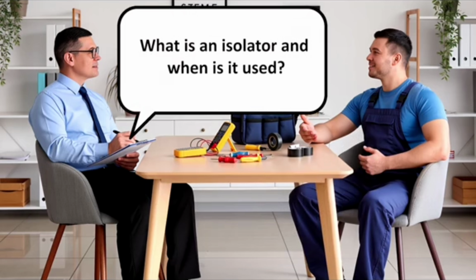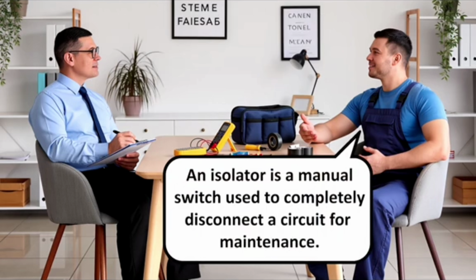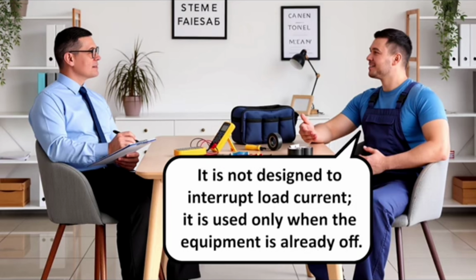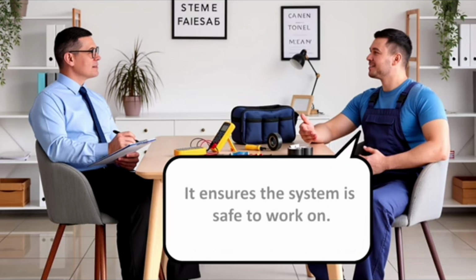What is an isolator and when is it used? An isolator is a manual switch used to completely disconnect a circuit for maintenance. It is not designed to interrupt load current. It is used only when the equipment is already off. It ensures the system is safe to work on.